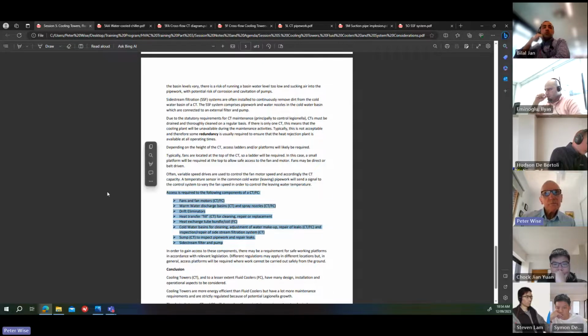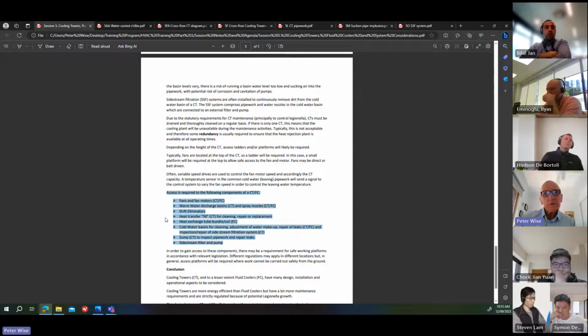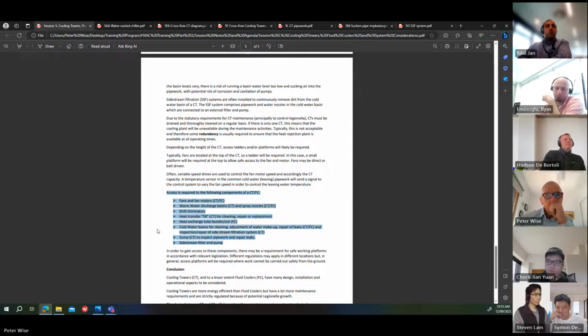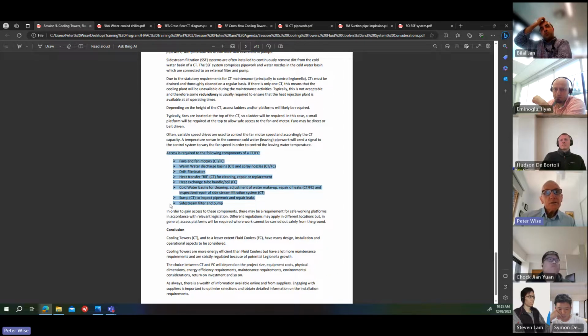So access is required to at least these components: fans and motors for a cooling tower and fluid cooler, warm water discharge basins and spray nozzles, drift eliminators, the heat transfer fill for cleaning, repair or replacement, heat exchange tube bundles in a fluid cooler, cold water basins for cleaning, adjustment of water makeup, repair of leaks. Water makeup is another thing that you need with a cooling tower and with a fluid cooler, because of the evaporation that's going on. So you've got to keep the water levels up. You need access for repair of leaks, inspection or repair of side stream filtration systems. In a cooling tower, you need to inspect pipework and repair leaks. You need access to the side stream filter and pump.